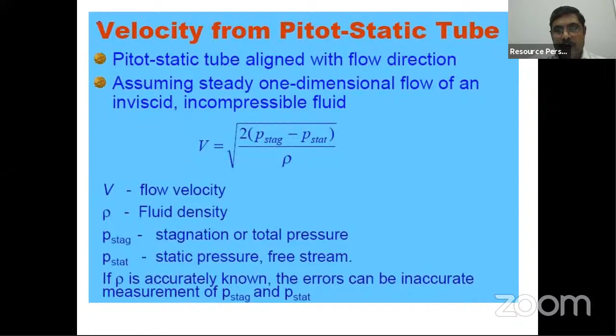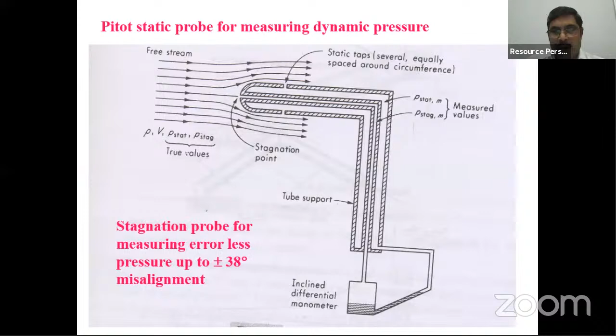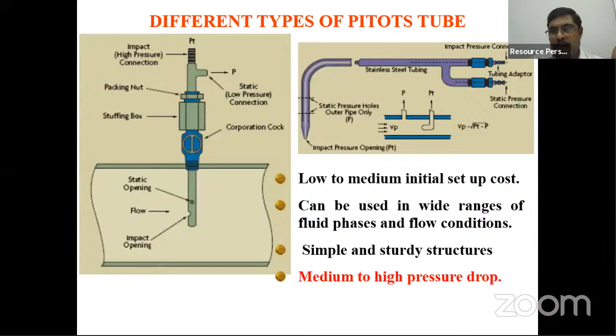But the only thing is, when you go for the pitot static probe, you have to go for this kind of spherical head. Basically, the spherical head gives the flexibility in aligning your tip within plus or minus 38 degrees. These probes need to be aligned parallel to the streamline. If there is an inclination, you will end up having an error. So if you choose the spherical head, it can accommodate some inclination. These are the different versions of this one. It can be used from low flow range to high flow range. It's very simple, and you can very easily insert it into the flow medium and get the flow rate.